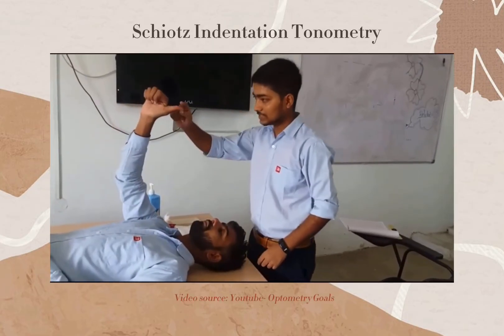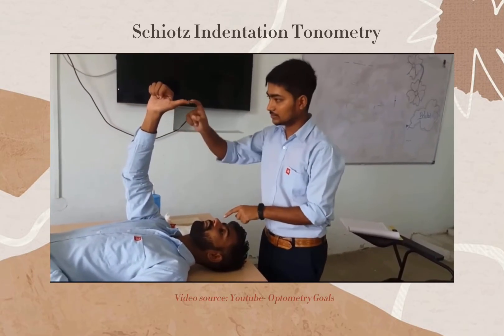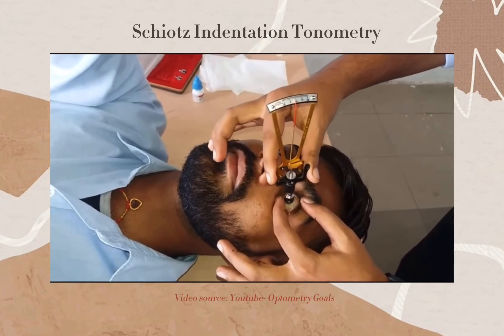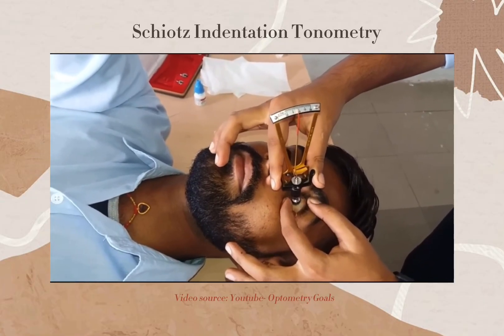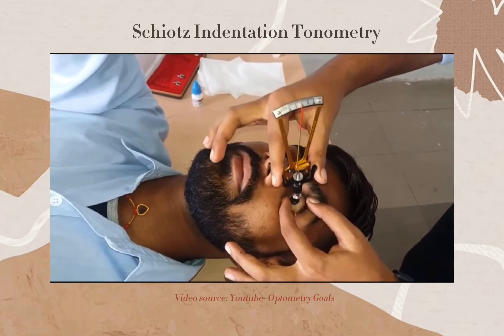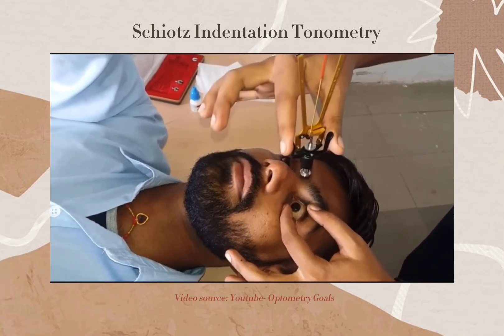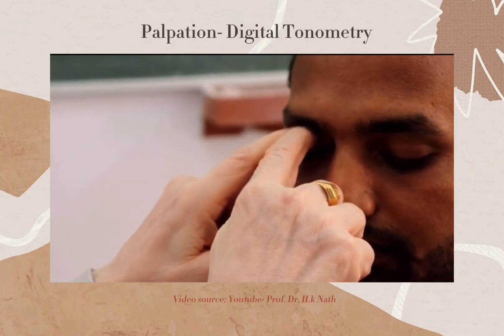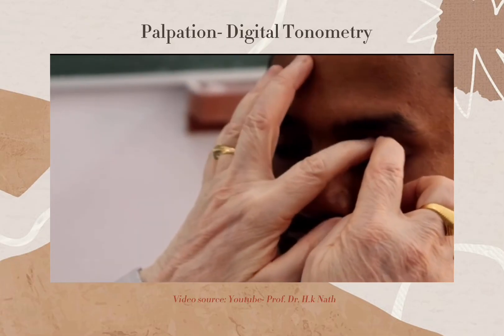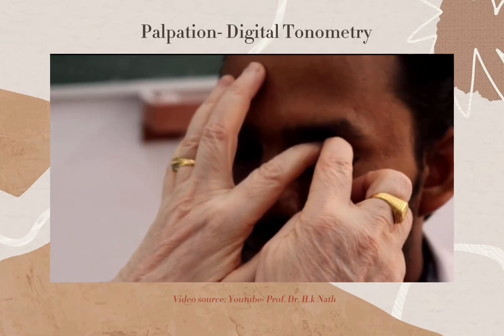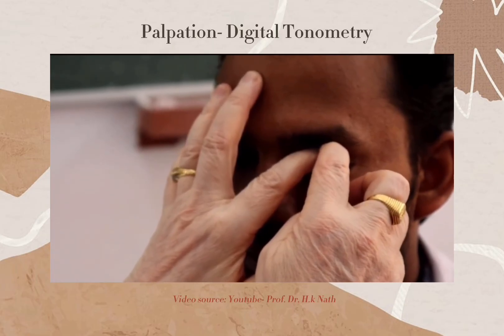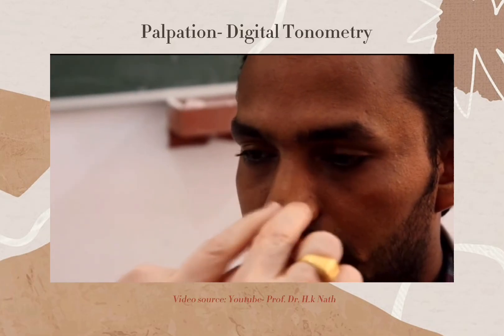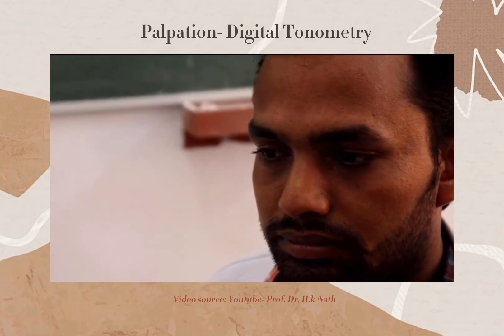On the other hand, the Schiøtz Indentation Tonometer is used to measure intraocular pressure by measuring the depth produced on the surface of the cornea by a load of known weight. The indentation of the corneal surface is inversely proportional to the intraocular pressure. Lastly, we have Digital Tonometry or the Palpation Method. The intraocular pressure is estimated by the response of the eye to pressure applied by a finger — a firm touch indicates normal intraocular pressure, while a hard one indicates high intraocular pressure.